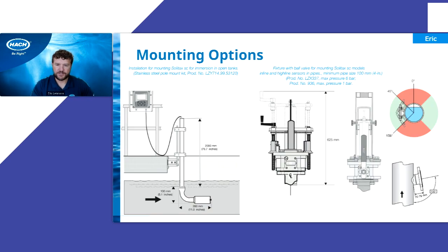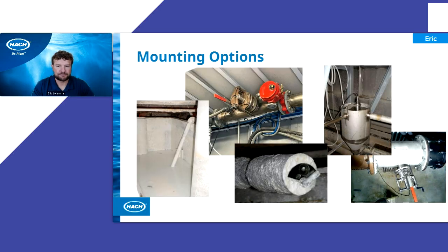This is specific to the Solitax probe. So we have the immersion mount, similar to the TSS-SC. We have the higher pressure safety armature, and then another safety type armature that really is for low pressure type applications. So again, it depends on where you're going to be installing these probes, what the application is. Just make sure we're selecting the right mounting configuration for that requirement. A great picture of some installations from some of our customers. Far left-hand side was in a pulp and paper plant, paper mill. Again, pretty aggressive applications. Up top there is the insertion type mounts and then the ball valve mounts.